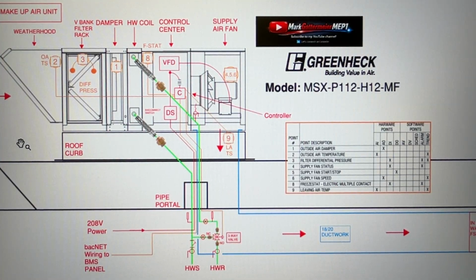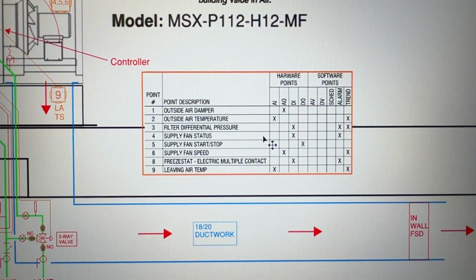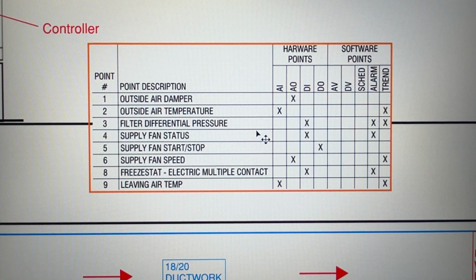So for the controls, let me slide over, there are some control points here. The control points would be your outside air damper, which is going to open up your airstream or close it depending on what it wants to do. This is an outside air temperature, we'll monitor what the outside air temperature is. Your filter differential pressure will be two probes. One will be on the inlet side of the filters and one will be on the discharge side of the filters, and it will compare the two to let you know how bad the filters are plugged up.